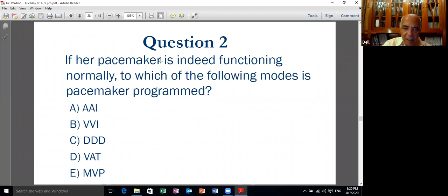Obviously, you don't find any pacing spikes here. So what happened here? We are putting the pacemaker at 60 lower rate limit. Here, the atrial rate is 80. So there is no pacing in the atrium because the native atrial rate is higher than 60. So there is no need for the pacemaker to work. So there must be an electrode in the atrium that's recognizing that the atrial rate is above 60. Now there is no pacing in the ventricle. So there is no electrode in the ventricle. Otherwise it will recognize that the ventricular rate was slow and pace the ventricle.